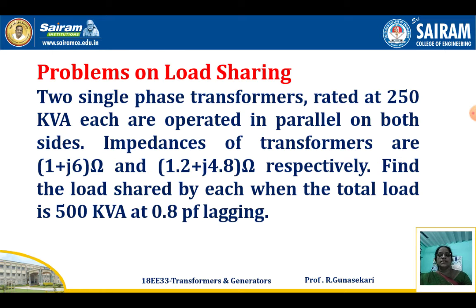So the meaning of this sentence is the total load, that is the capital S, is 500 kVA. That means the load shared by both transformers is 500 kVA. At that time the power factor is 0.8 lagging. Now the required data is the load shared by each transformer.